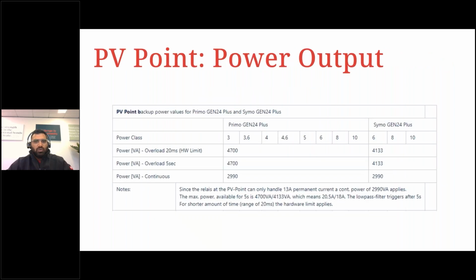Right. So what are the capabilities of PV Point? If you look at the output power ratings, you can see that for both single phase and three phase models, the continuous power rating is about 3 kilowatts. But for a 5 second overload, the Primo inverters, or the single phase inverters, have about 4.7 kilowatts possible, whereas the three phase inverters have 4.1 kilowatts. Please note that it is possible on all inverters, not just from 6, 8, and 10, actually all the way from 3 to 10 on Symo, you can still do PV Point.